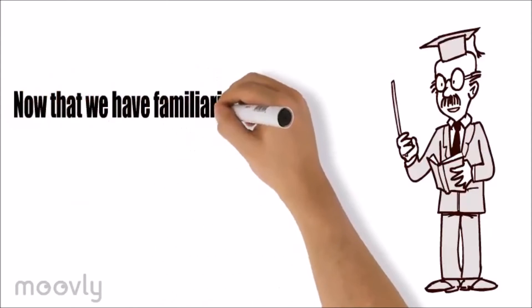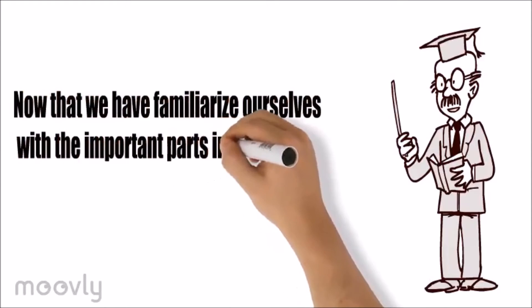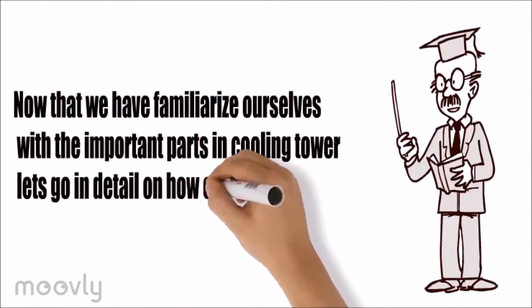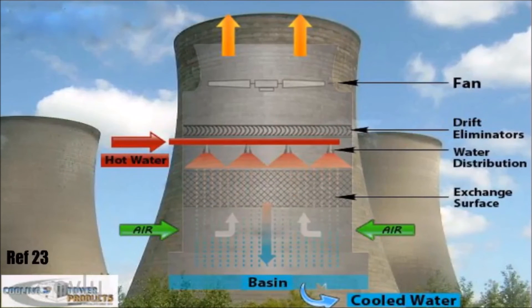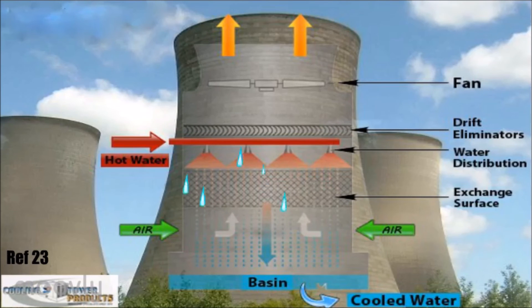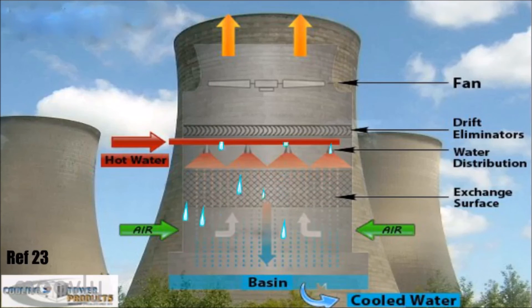Now that we have familiarized ourselves with the important parts of the cooling tower, let's go into detail on how exactly cooling towers work. Open cooling towers expose the hot water coming from the reactor's condenser directly to the atmosphere. This warm water is pumped to the nozzle by the condenser pump and is sprayed over the tower packing to increase the contact area, and air passes through the packing. There are some towers that feed the nozzles by gravity, using a water distribution basin. Most of the heat is removed by evaporation.